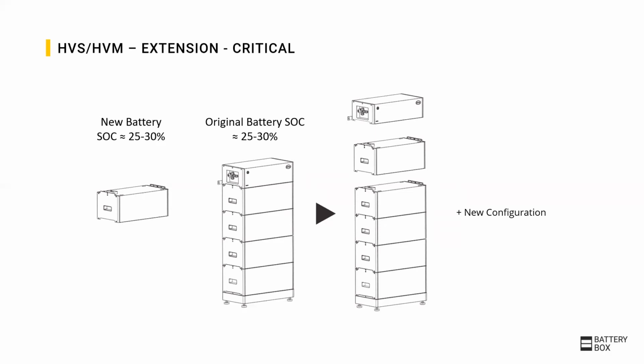We recommend involving the end customer, who can simply switch off the existing system at 25 to 30% by pressing the LED button, so that the installer only has to insert the new module and reconfigure the system. The same state of charge in all modules is necessary because of the direct series connection of the modules without a DC-DC converter. This, in turn, is responsible for the very high efficiency of the system.